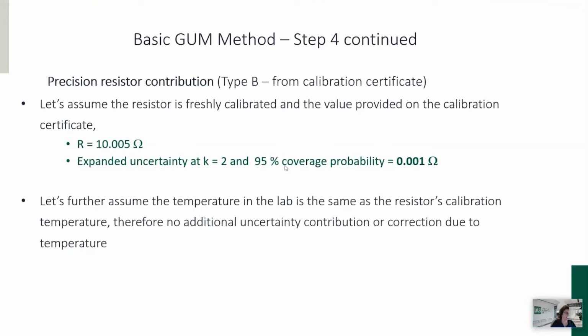On that calibration certificate, there was a calibration uncertainty given. Let's say this value was given with an uncertainty of 0.001 ohm or 1 milliohm, and they also gave a K factor of 2 to get to a 95% coverage probability. Again, ILAC P14, the ILAC policy on measurement uncertainty that applies to calibration laboratories, tells us that measurement uncertainty should be reported, and the GUM does too. The GUM says 95% or above, ILAC P14 says 95%, and this is a coverage factor K equal to 2, which we will explain in a few more slides.